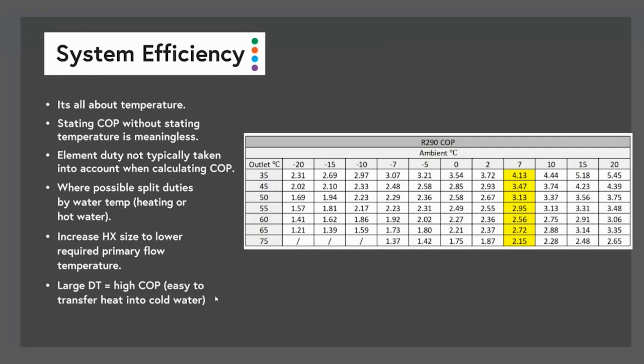Another figure that they use typically is 35-degree water temperature. So that would be the number on the top row, 4.13. So this heat pump at 7 degrees outside and 35-degree flow temperature is producing a COP of 4.13, or is 413% efficient. That's a very, very good number. However, 7 degrees isn't particularly cold, and 35 isn't particularly hot. So that's not really a realistic full load condition. It's maybe a bit of an average for some of the country, because 35 is even a low flow temperature for underfloor heating.